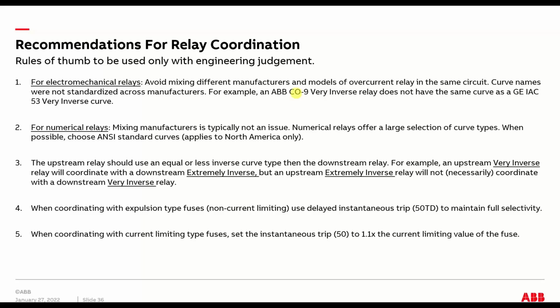For electromechanical relays, I think I've been through this. The various manufacturers all had different curves with the same name. So there may have been a CO9 very inverse from ABB that wasn't the same curve as what GE called a very inverse, which would have been an IAC 53. So the take home is, if you're in an electromechanical world, avoid mixing different manufacturers and models. It can be done, but it makes your life more difficult because they're not the same type curves. Most of you probably won't get into that situation anymore because you're not speccing new electromechanical relays.